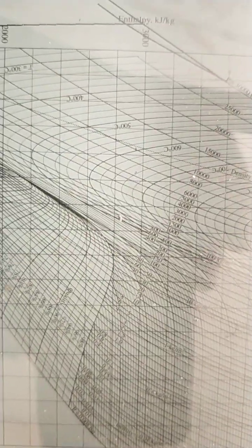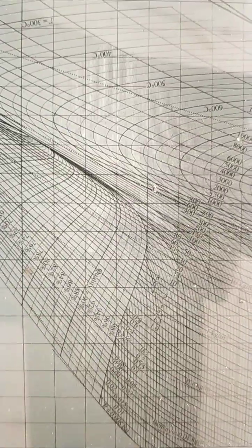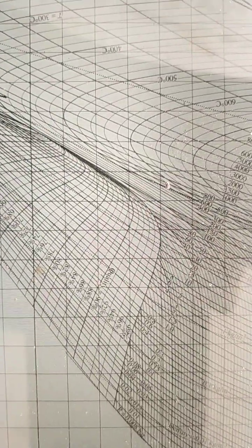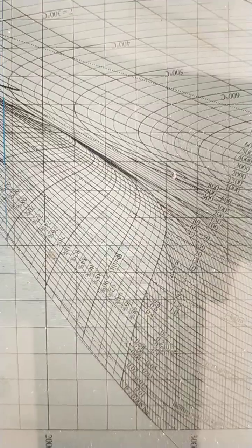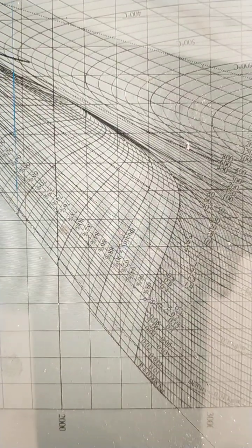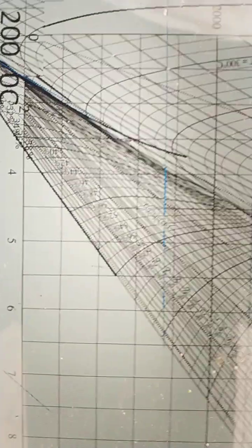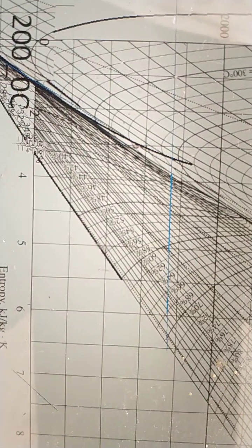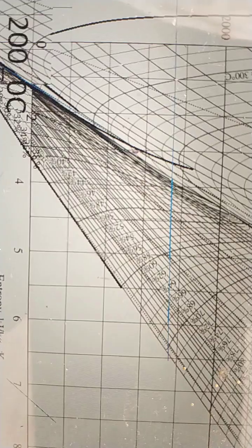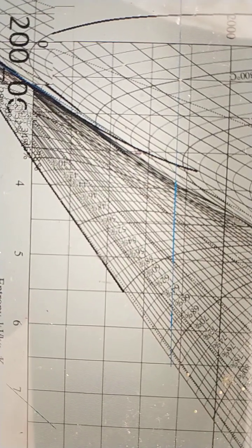And then for the quality, 98% is here. Above this line is 100%. You have full steam, no water. And then it goes down in steps of 2 roughly. So you get 40% at this line.